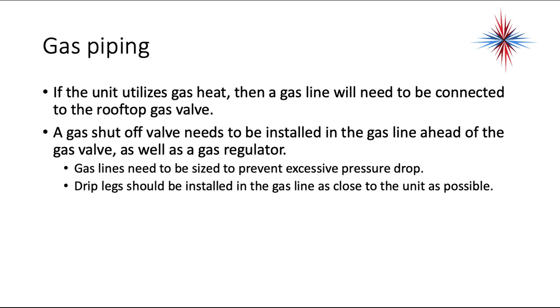If the unit utilizes gas heat, then a gas line will need to be connected to the rooftop gas valve. A gas shutoff valve needs to be installed on the gas line ahead of the gas valve as well as the regulator. Gas lines need to be sized to prevent excess pressure drop. Drip legs should be installed in the gas line as close to the unit as possible.